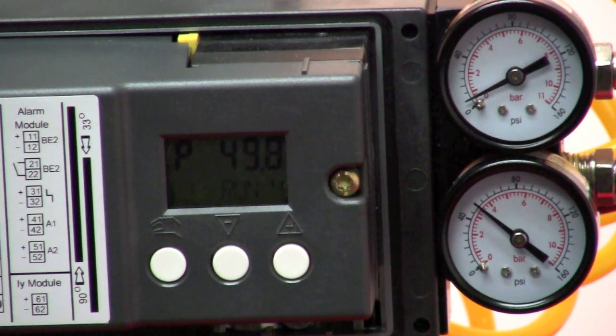Run mode 4 measures the minimum amount of air required to move the valve at every point during its stroke, along its stroke.